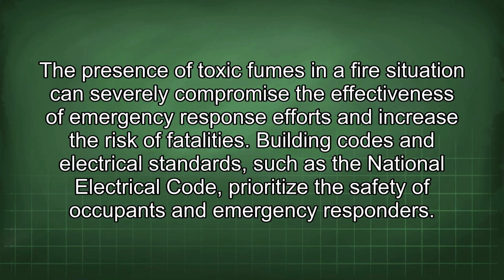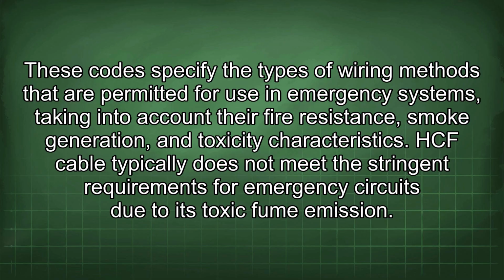the risk of fatalities. Building codes and electrical standards, such as the National Electrical Code, prioritize the safety of occupants and emergency responders. These codes specify the types of wiring methods that are permitted for use in emergency systems, taking into account their fire resistance, smoke generation, and toxicity characteristics. HCF cable typically does not meet the stringent requirements for emergency circuits due to its toxic fume emission.